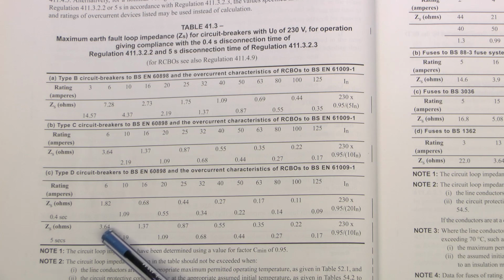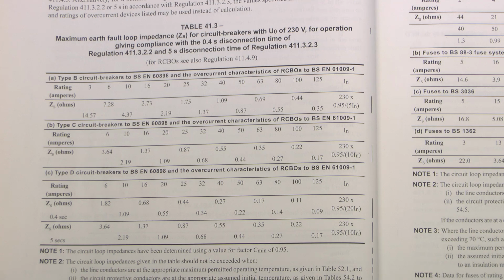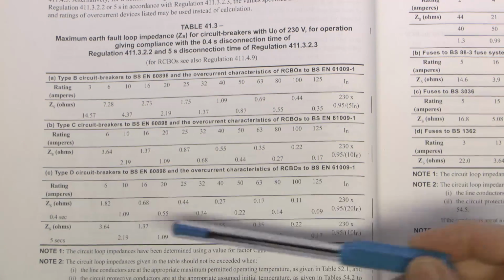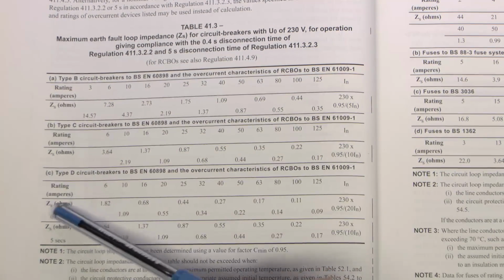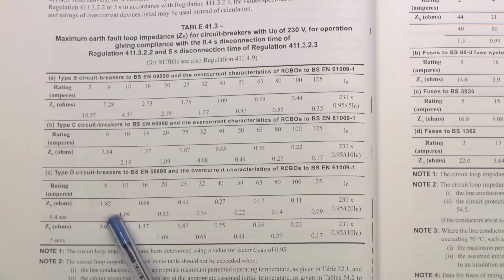In these cases, you can have a somewhat higher impedance there, but 5-second disconnection is not applicable to quite a lot of circuits, though in some cases that can be used. But we'll have a look at the disconnection times at a later date.